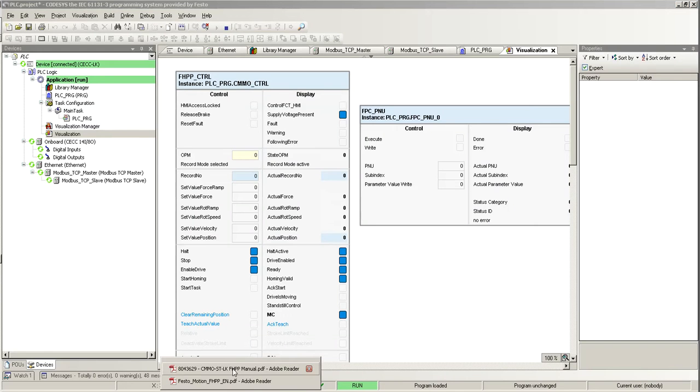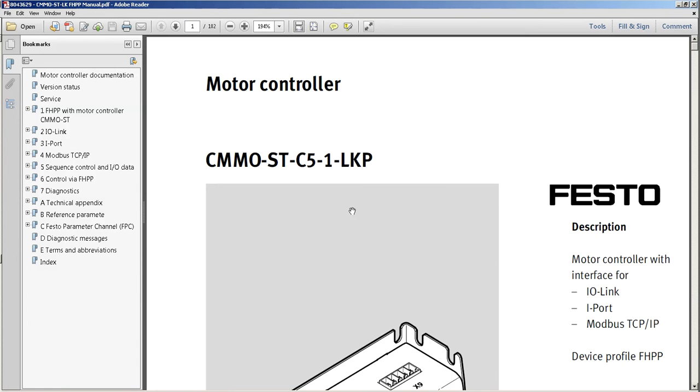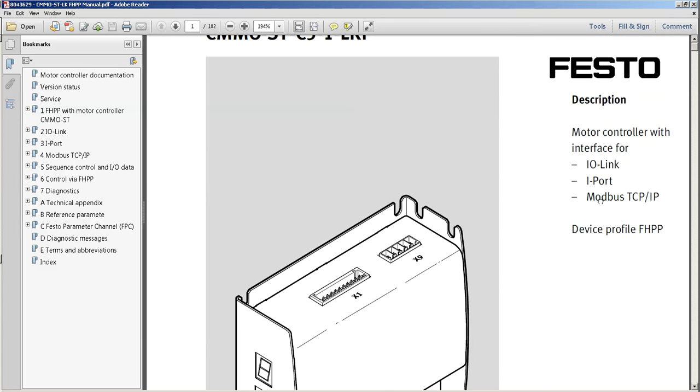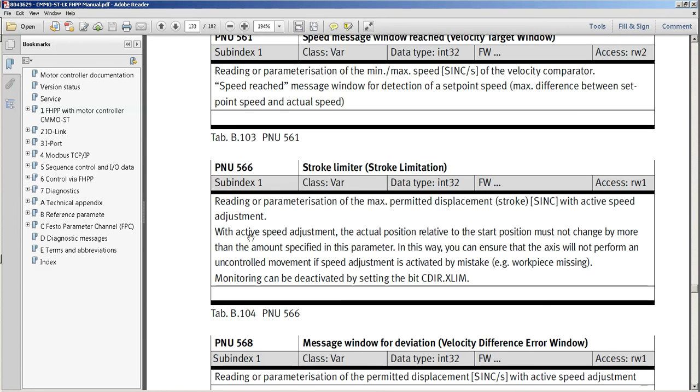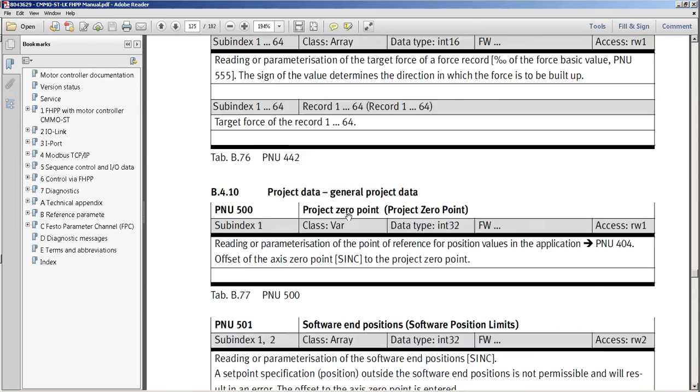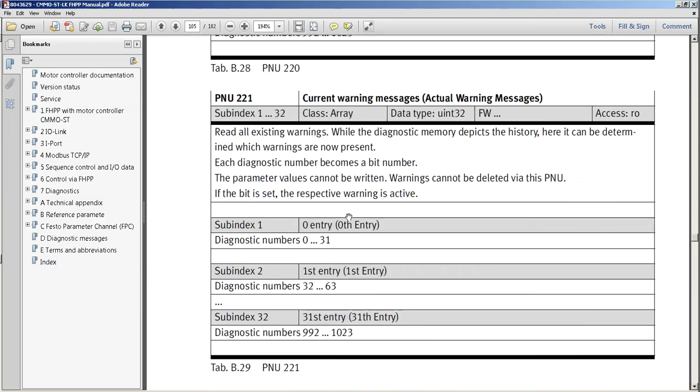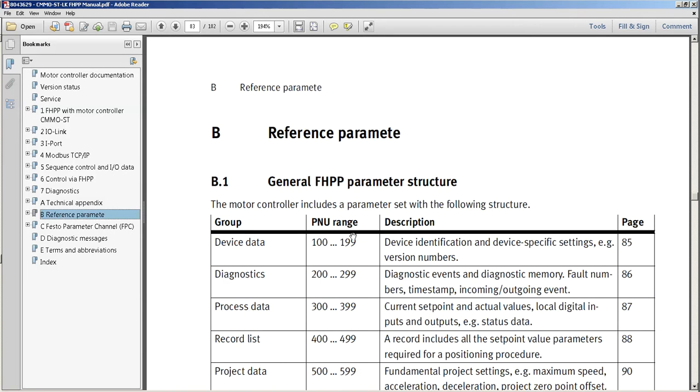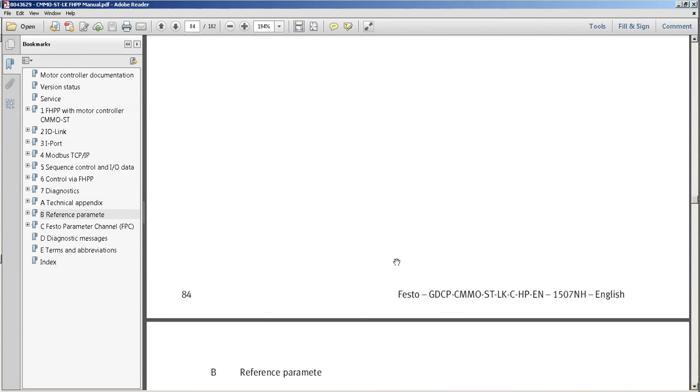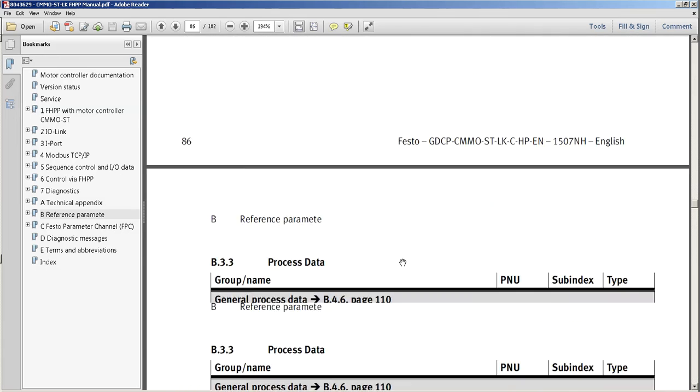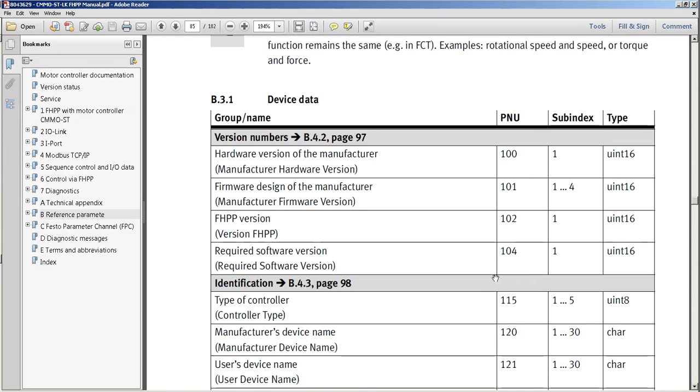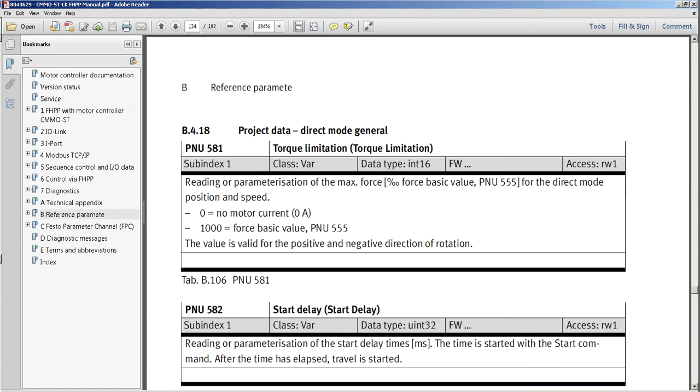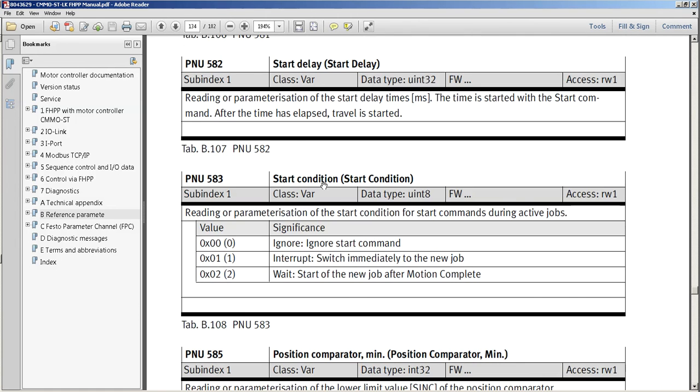If you download this manual, which is the motor controllers, you look for this part number on the support portal, and then you get this FHPP manual. This is the description of all of the parameters that you can write. Each parameter has a number, PNU, and then there's a number for each parameter. Right now, I'm going to focus on 583, start condition.